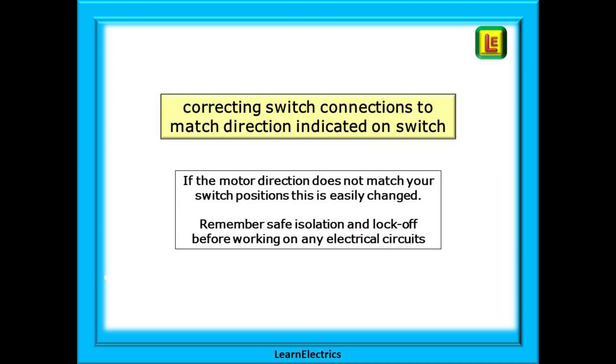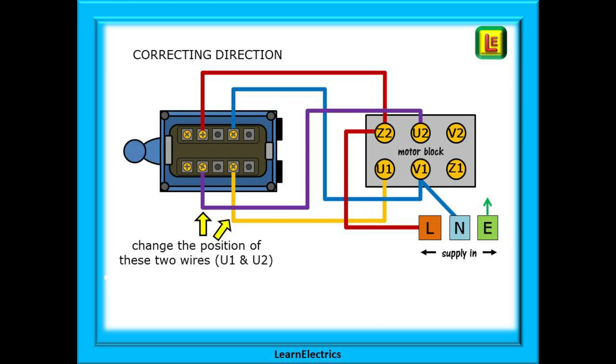The second variation is when the drum switch says forwards and the motor is moving in reverse for the customer's expectations, and when in reverse the customer says that that is his forwards direction. So if the motor direction does not match your switch positions this can easily be changed. But do remember safe isolation and lock off before working on any electrical circuits. All we need to do is to change the U1 and U2 connections over shown here by the two yellow arrows. Do not change the phase and neutral and hey presto the switching directions have been changed.